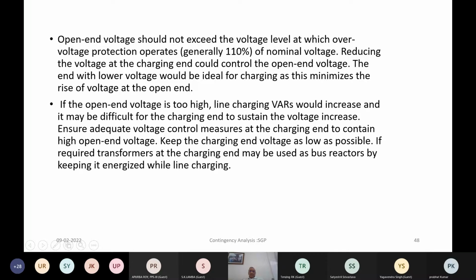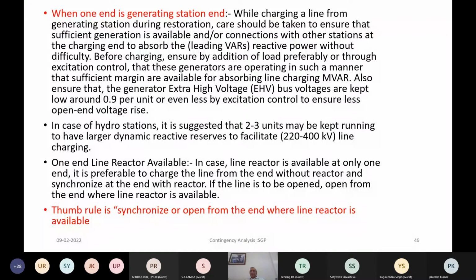In some of the stations where the line lengths are large, it is a good practice to also line up the line on dead and then build up the voltage slowly by controlling the excitation on manual mode. So that is also being practiced. When one end you have a generating station and you have a line charging task, in AVR also there is a provision to have line charging capability where excitation can be built up slowly on manual mode to charge the line, so that you ensure that over voltages do not happen and the leading reactive can be absorbed by the generator as you build up the voltage slowly. So this is another way to control the voltages when you are doing the line charging.